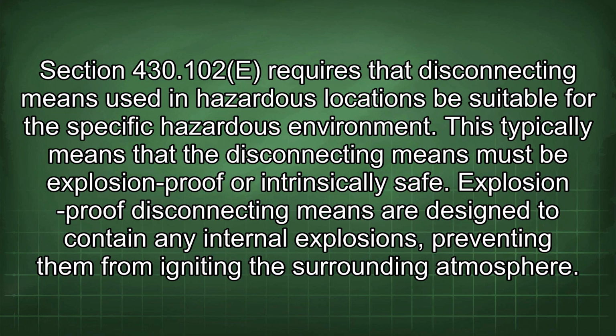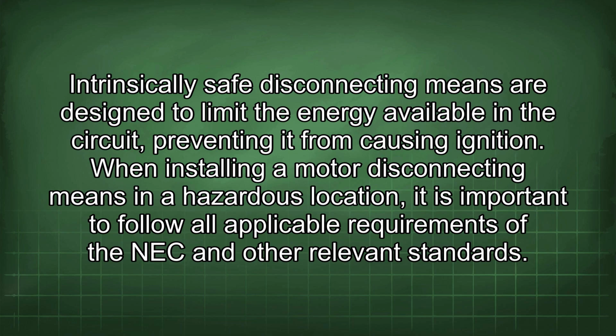This typically means that the disconnecting means must be explosion-proof or intrinsically safe. Explosion-proof disconnecting means are designed to contain any internal explosions, preventing them from igniting the surrounding atmosphere. Intrinsically safe disconnecting means are designed to limit the energy available in the circuit, preventing it from causing ignition.